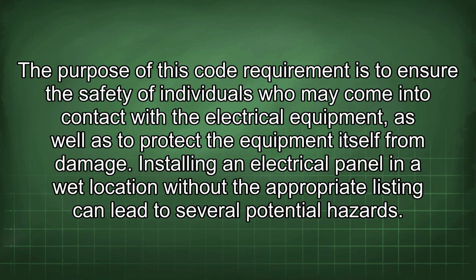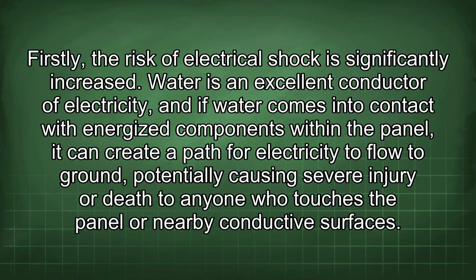The purpose of this code requirement is to ensure the safety of individuals who may come into contact with the electrical equipment, as well as to protect the equipment itself from damage. Installing an electrical panel in a wet location without the appropriate listing can lead to several potential hazards. Firstly, the risk of electrical shock is significantly increased. Water is an excellent conductor of electricity, and if water comes into contact with energized components within the panel, it can create a path for electricity to flow to ground, potentially causing severe injury or death to anyone who touches the panel or nearby conductive surfaces.